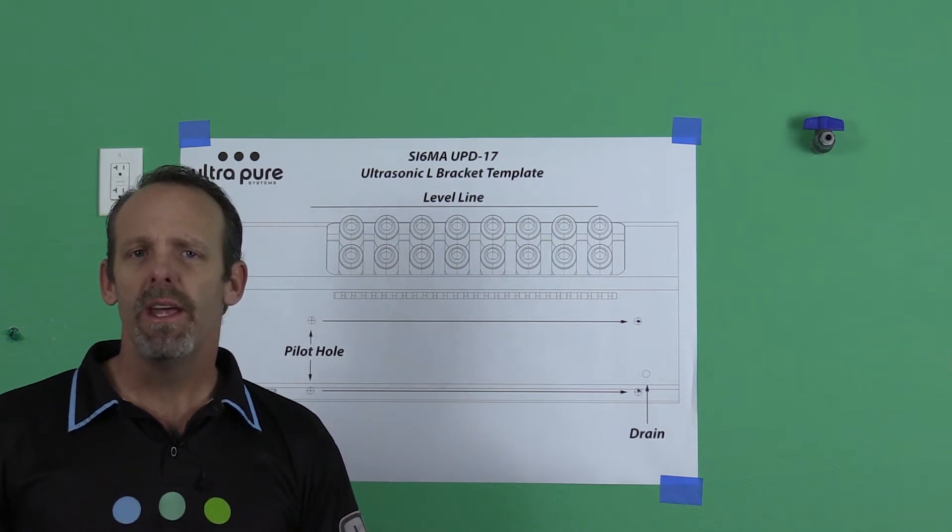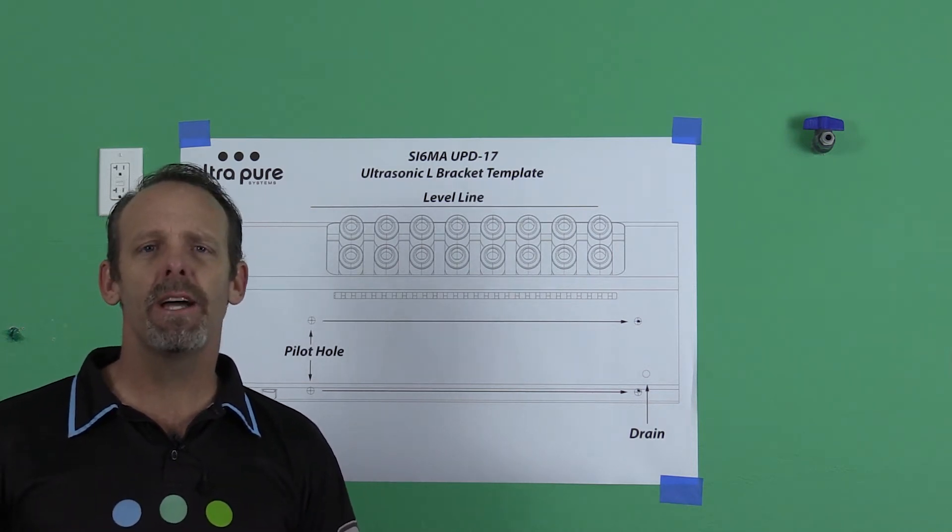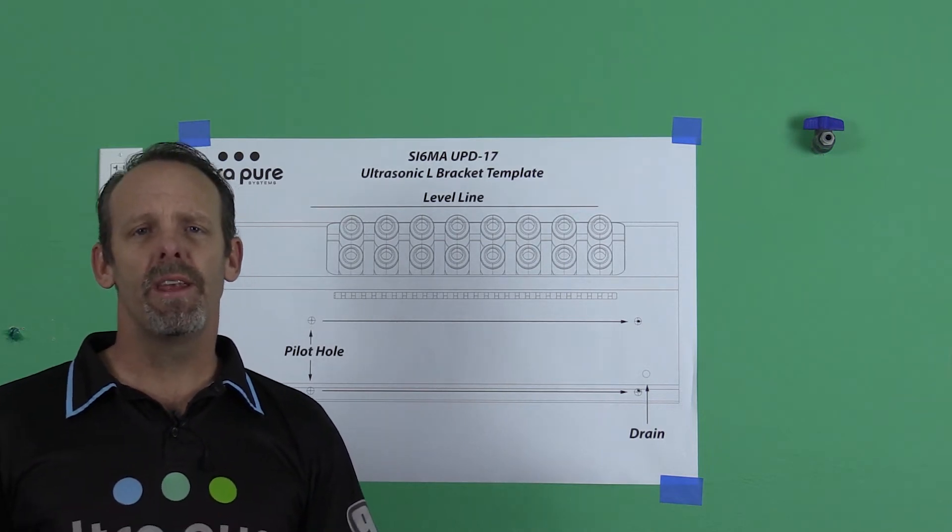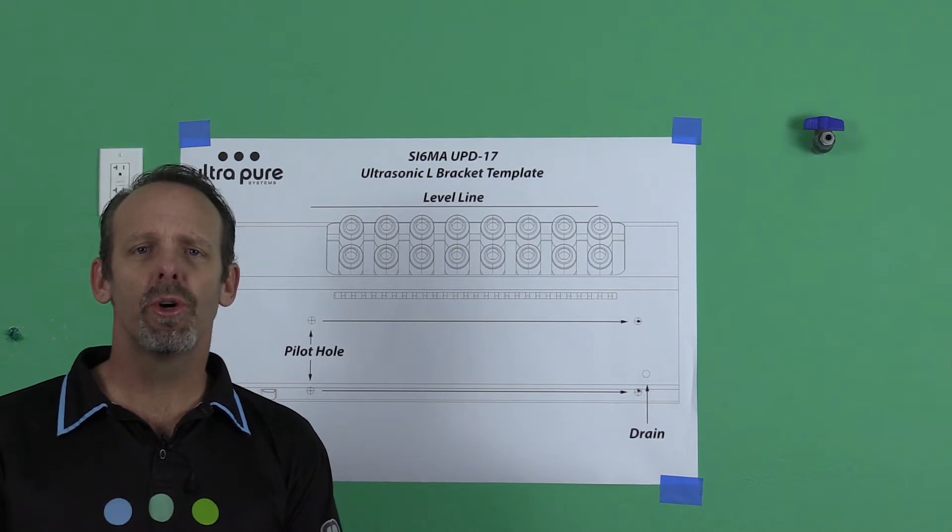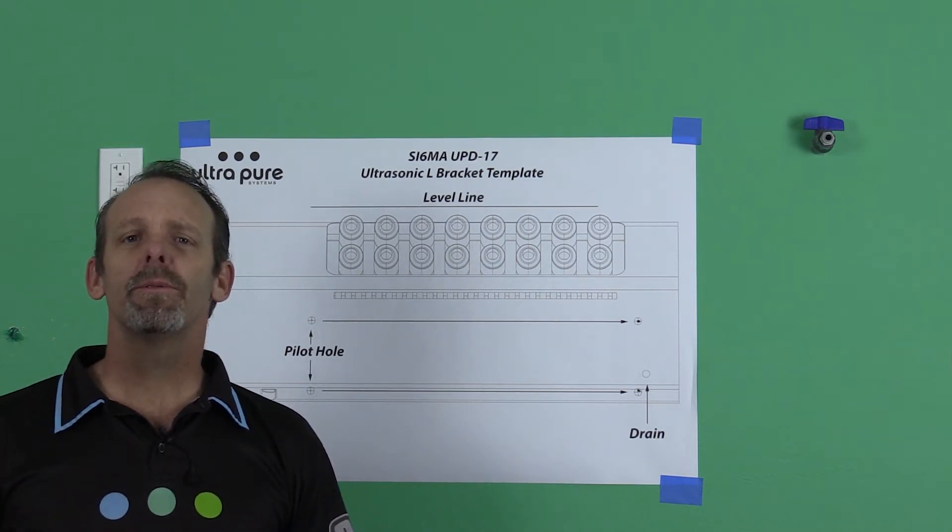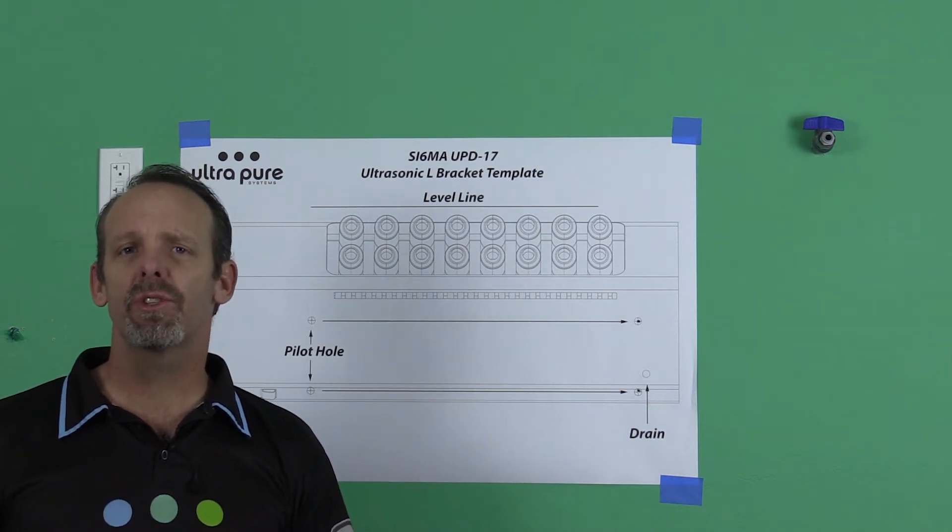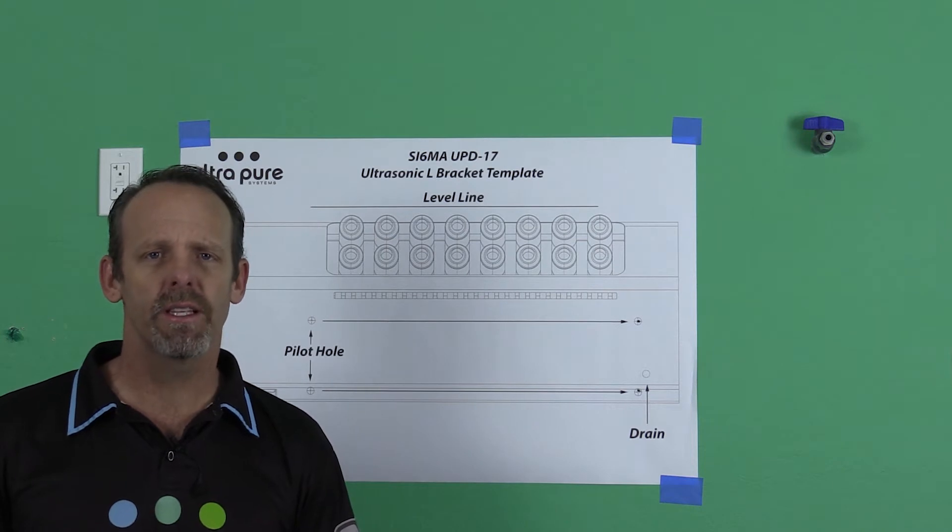One of the things we talk to our technicians about is drawing an imaginary box during the installation, and nothing can be in that imaginary box. That way, you could be confident that the mist is going to get absorbed into the airstream. One of the problems that we have found in the installation phase is the guys installing it just don't know that. And it's a very important part of installation.